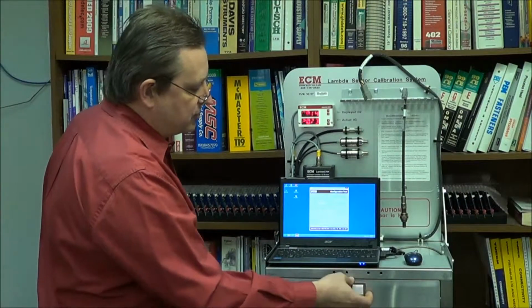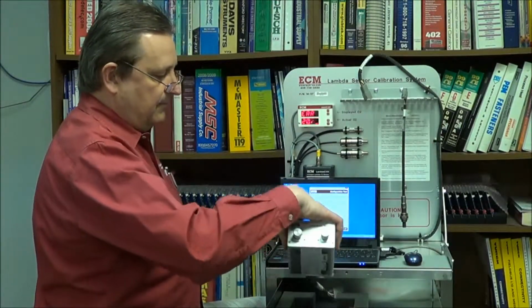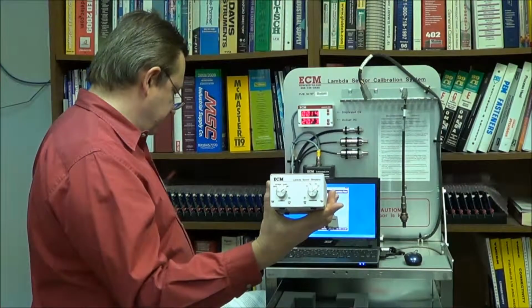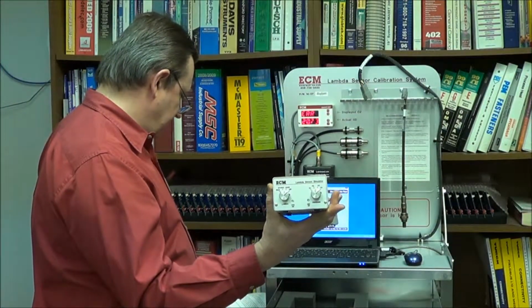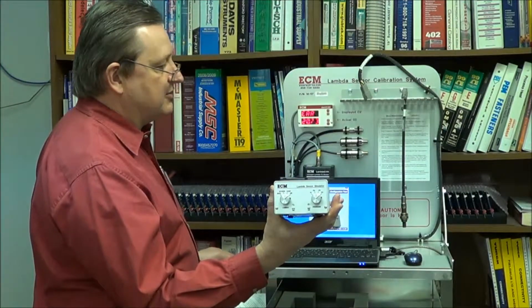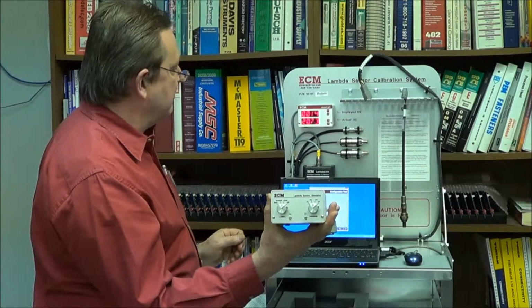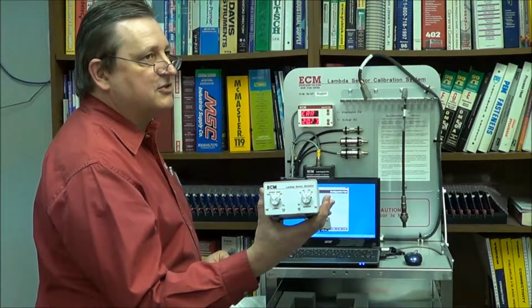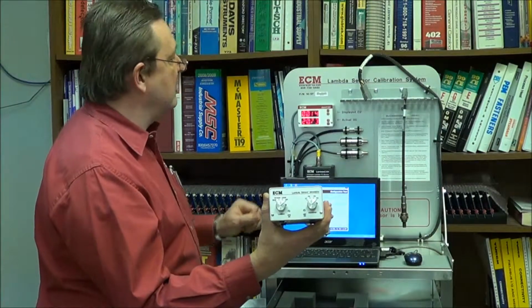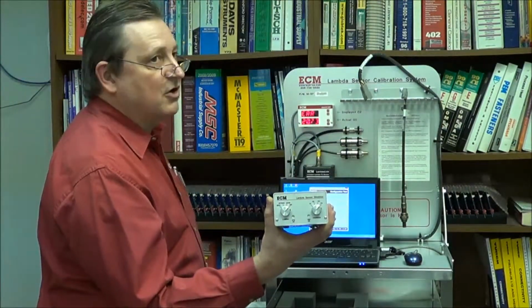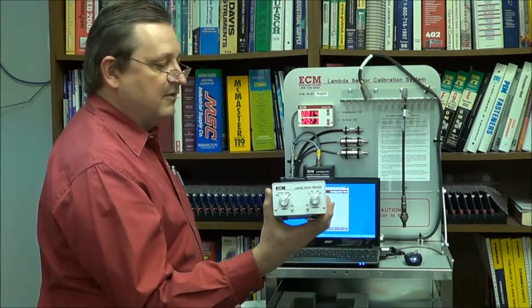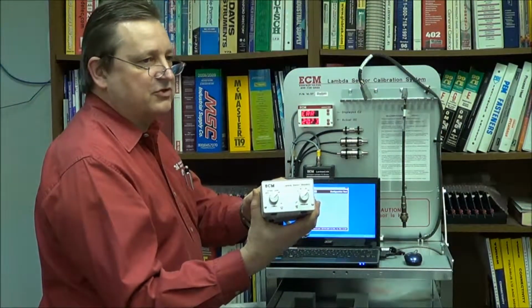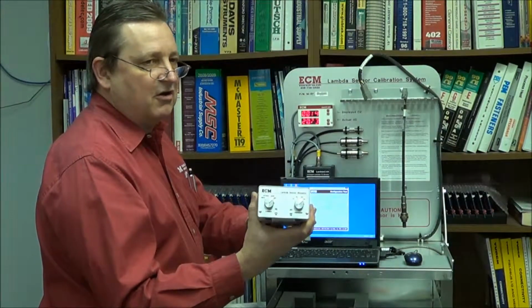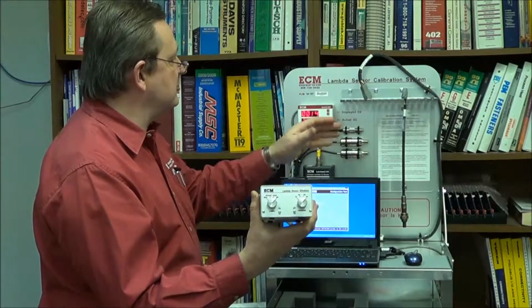The ability for the system to accurately measure current is verified by the sensor simulator, which is a precision current and voltage source. Here is a sensor simulator. I'm going to demonstrate the use of the sensor simulator to verify that this Lambda can is properly measuring currents output by the Lambda sensor and by voltage outputs from the pressure sensor, which performs a pressure compensation. This is a precision current and voltage source, and you can send this back to us once a year to have it calibrated with these three sensors.